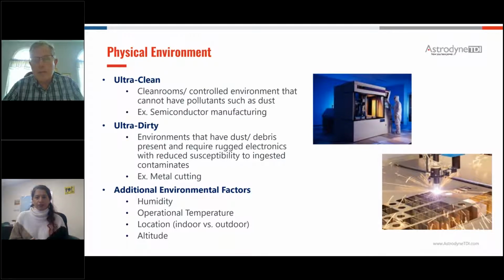Operational temperature: make sure the power supply is properly rated for the effective temperature surrounding it and its application. We've seen applications with out-of-door requirements where there's an IP rating, where the power supply has to work in a driving rainstorm and things like that. And the other thing we've seen lately is altitude. Most power supplies are typically rated up to 10,000 feet, but we've been seeing requirements for cities at higher altitudes than that. As altitude goes up, the effectiveness of cooling air goes down, so you need to be careful in that regard when specifying the power supply and understanding the environment.